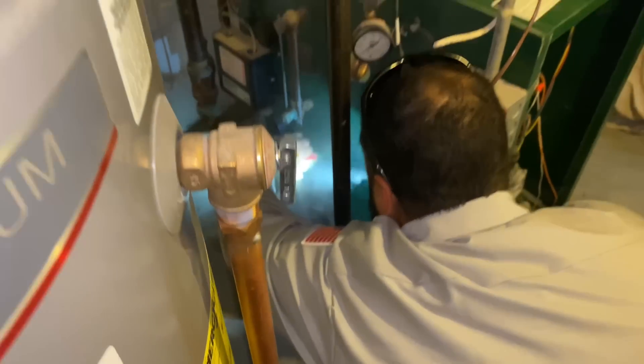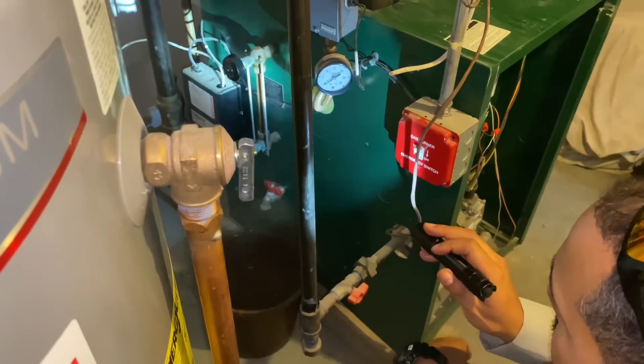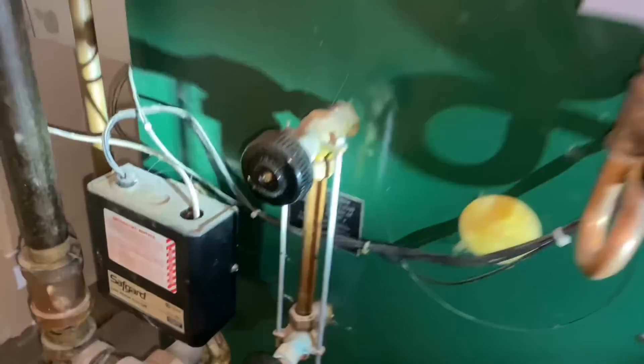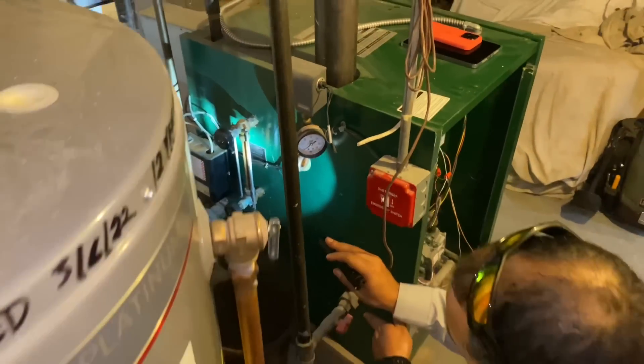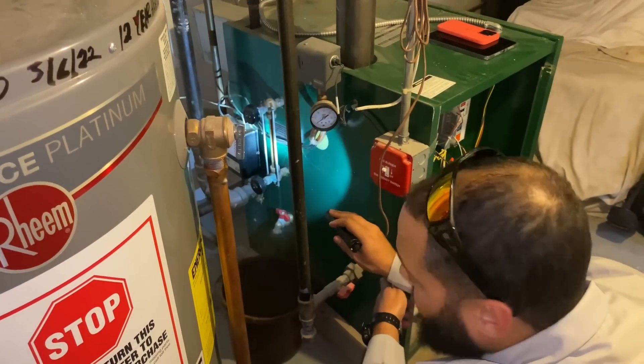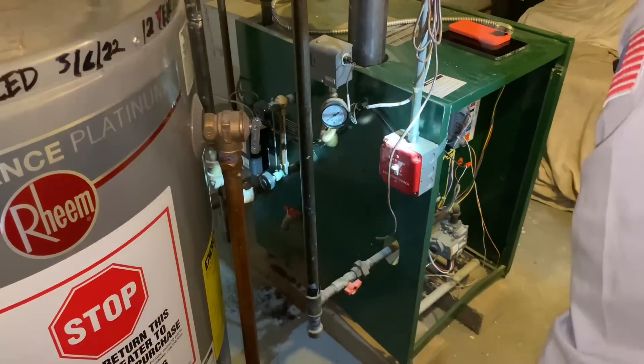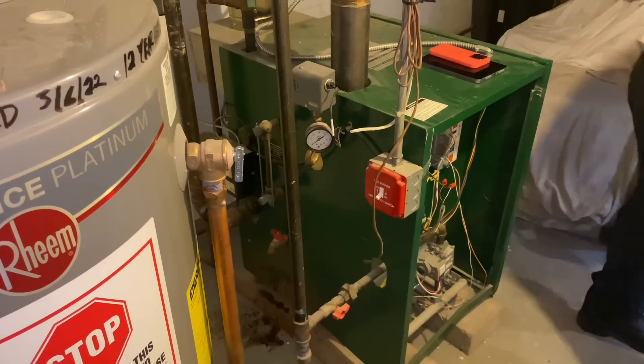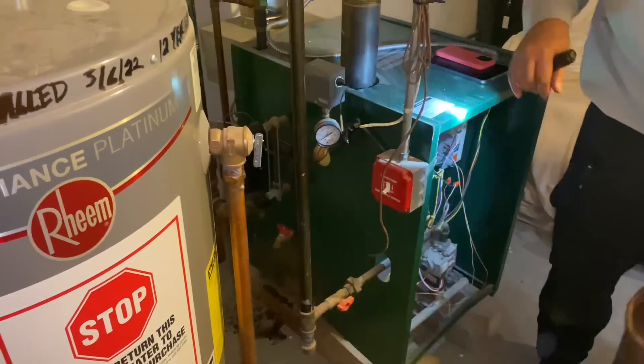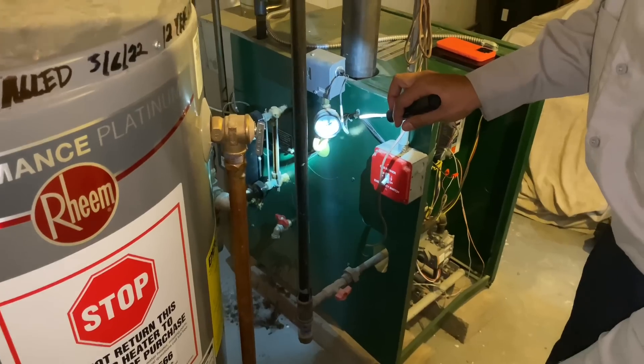We have Jose and it looks like he's draining water. Jose, let me ask you a question - you're draining water, right? Why? Because it looks like the sight glass is way past the full level, but it could just be dirty also. So we're going to have to take that out, clean it out so we can gauge the correct water level. What's your first step right now? What's your second step? Empty the bucket, come back, close the valves, then take out the sight glass.